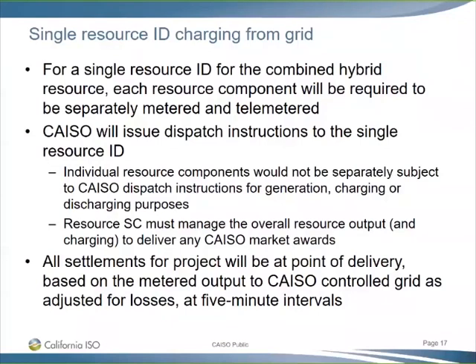This is Chris again. I'd add that the upper amount you can actually inject at any given time is really limited by whatever your point of interconnection rights are. If you requested 200 or 400 megawatts in the interconnection process, whatever you establish as your point of interconnection injection rights is the upper limit you can ever put onto the grid at any given time. That's why we require tripping-type control schemes to avoid exceeding that amount of energy injected in an instantaneous time frame.